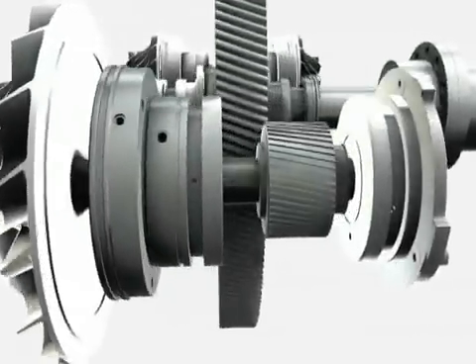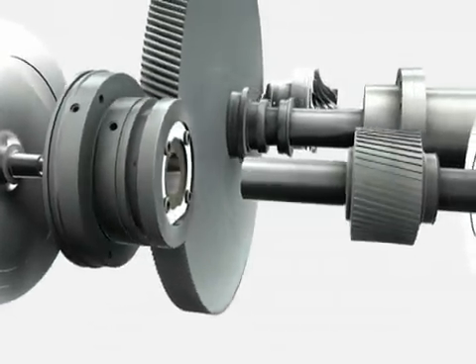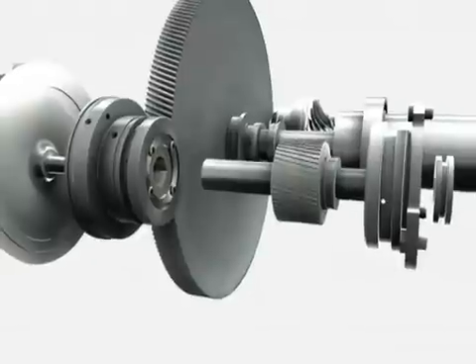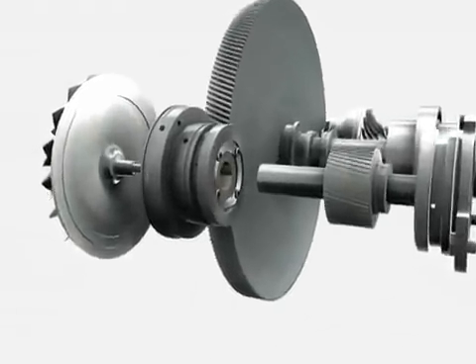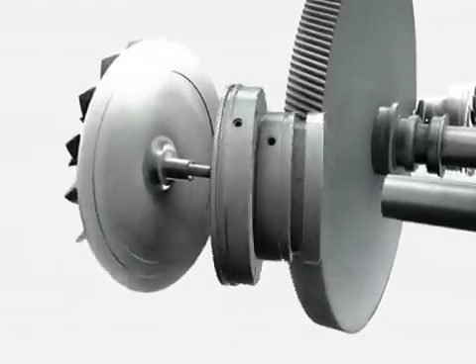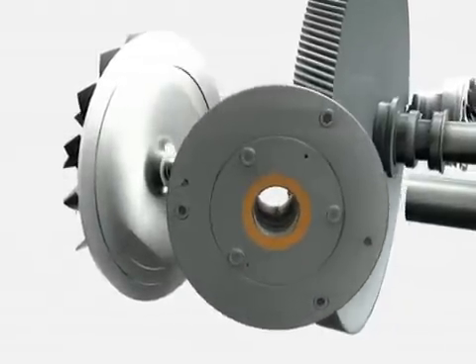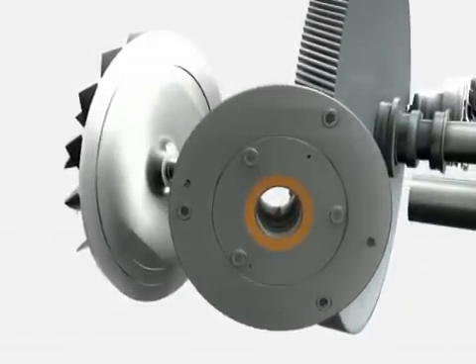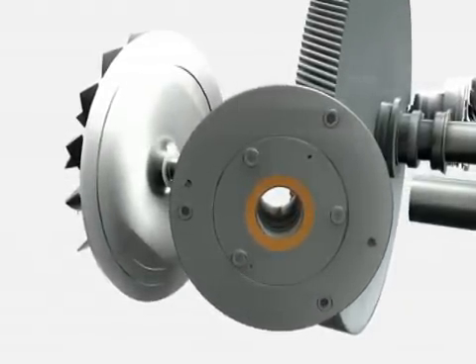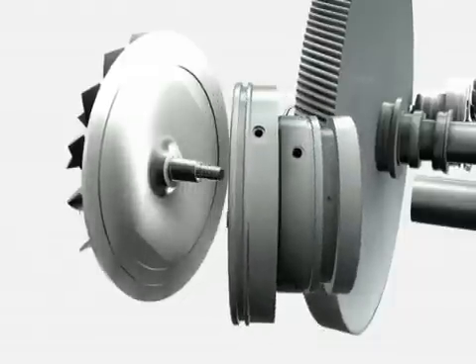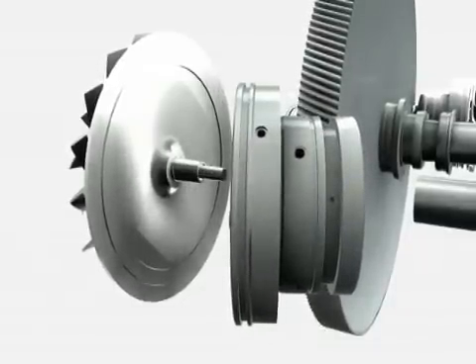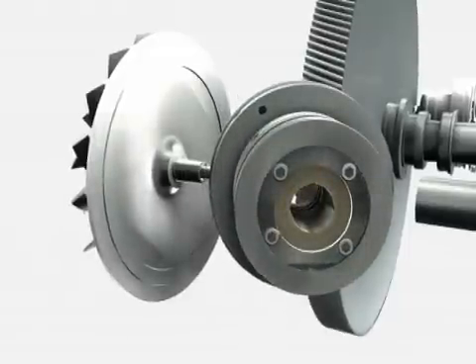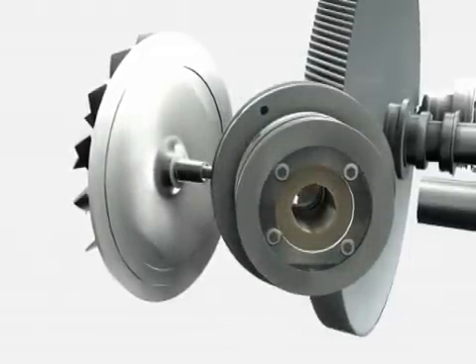The assembly rides on a thin film of oil separated from the air by non-wearing carbon ring seals, ensuring 100% oil free ISO class zero air in all operating conditions, including being unloaded. Single piece carbon ring seals minimize air loss by more than 50% when compared to labyrinth style seals, which could save users more than 140,000 kilowatt hours of electricity per year.